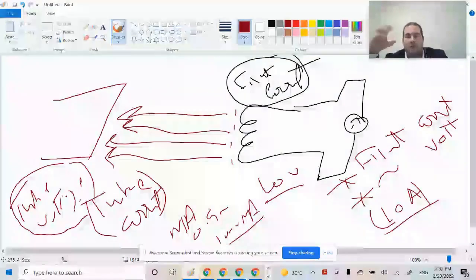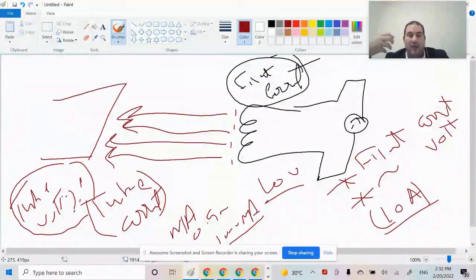If the filament current increases, the number of electrons moving across the filament will increase. To increase the tube current, you need to increase the filament current to provide a greater number of electrons moving from the cathode to the anode. Therefore, the tube current is highly dependent on the filament current, while the tube voltage is unrelated to the filament voltage. You must distinguish between the two.